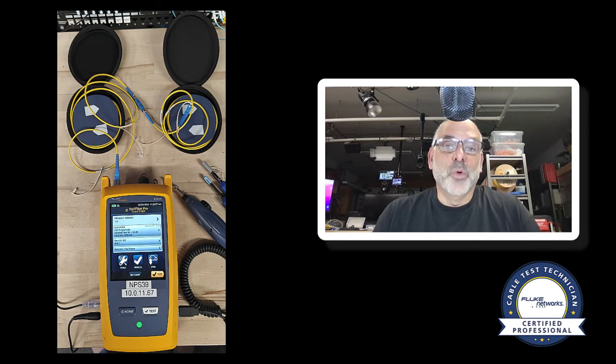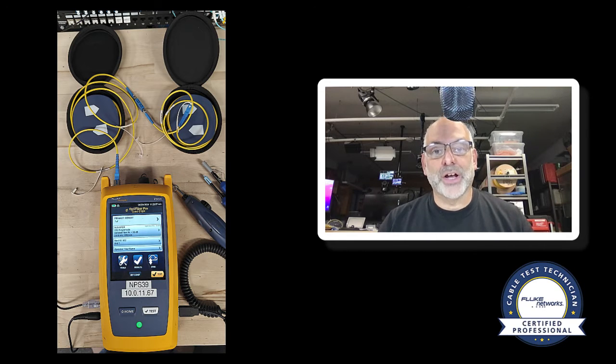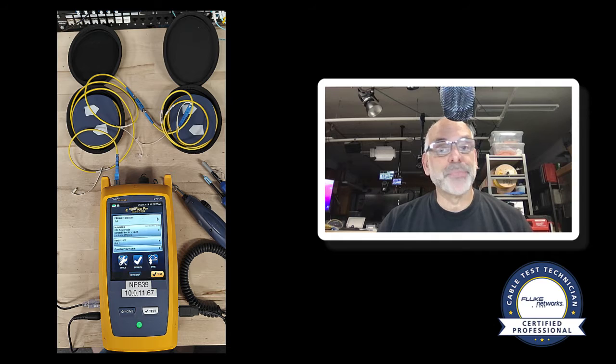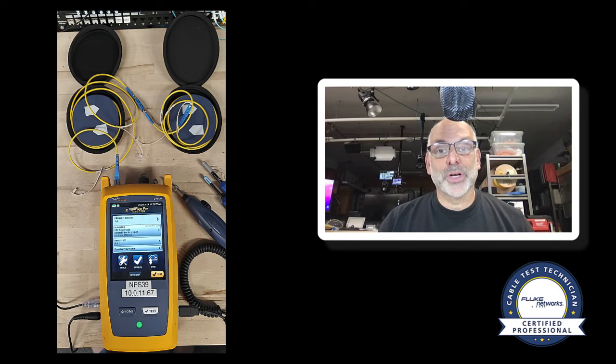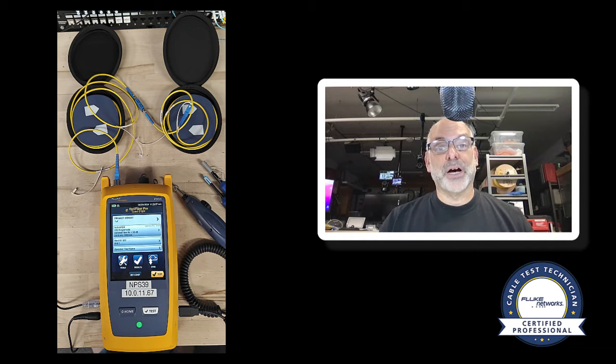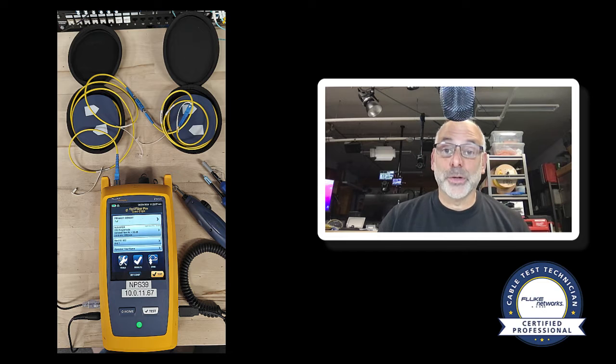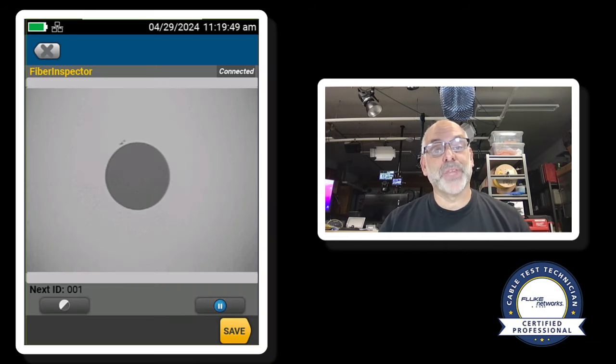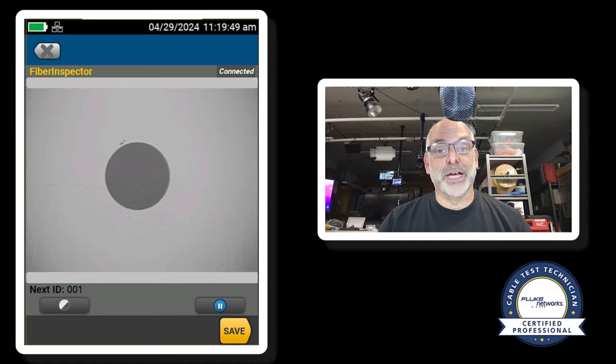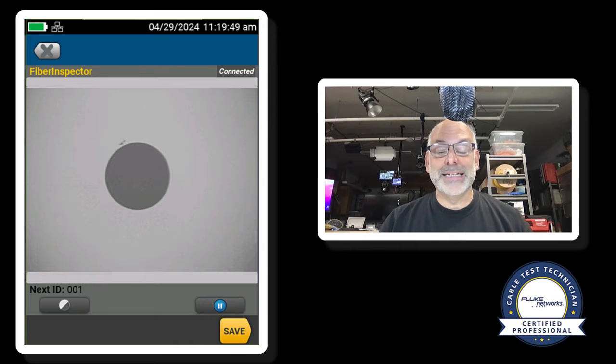So here we can see what the test equipment looks like when we've got it all set up. Now before connecting any of the fibers, I inspected the port on the OptiFiber Pro single-mode port, and this is what it looked like. So it looked good. I didn't need to do anything. I didn't need to clean it.